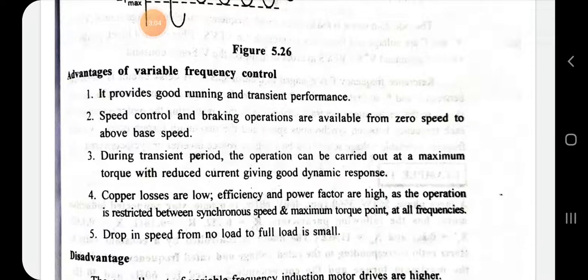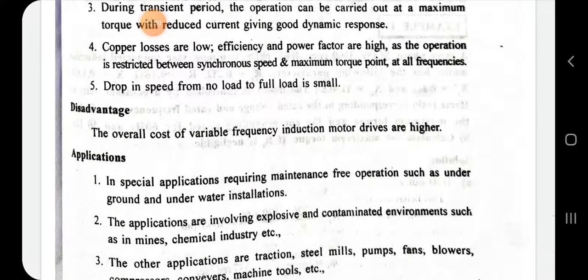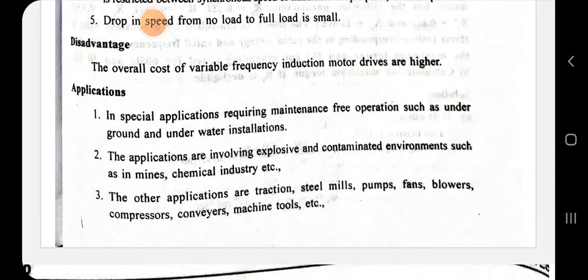Advantages of V/f control: it provides good running and transient response; speed control from zero speed to above rated speed is possible; braking operation is also available; maximum torque with reduced current and good dynamic response; copper losses are low; efficiency and power factor are high; operation is restricted between synchronous speed and maximum torque point; and drop in speed from no-load to full-load is very small. The disadvantage is that the cost is very high. Applications include mines, chemical industries, traction, steel mills, pumps, fans, blowers, compressors, conveyors, and machine tools.